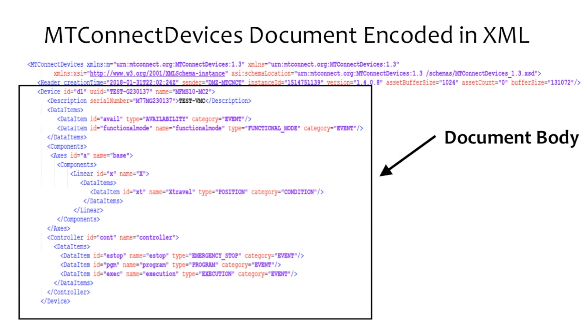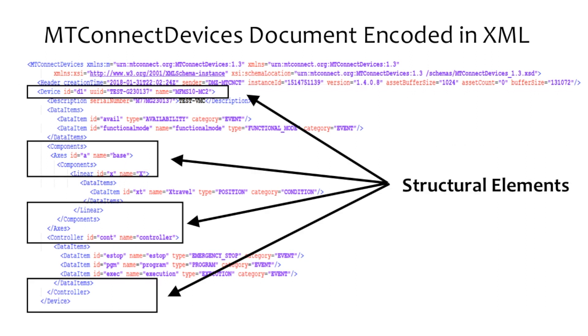Both data models utilize two types of XML elements to describe the organized information: structural elements and data entities. Structural elements define the physical and logical parts and sub-parts used to describe a piece of equipment. Higher-level structural elements describe major functions like the machine controller, each of the axes, the enclosure, and safety equipment. Lower-level structural elements describe smaller sub-parts such as motors, valves, tanks, or a door.